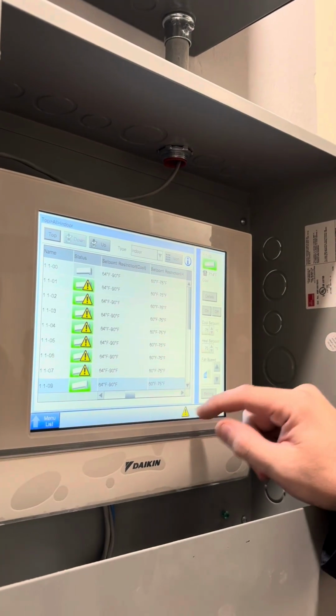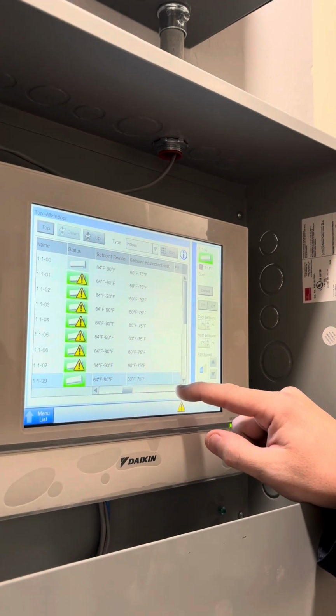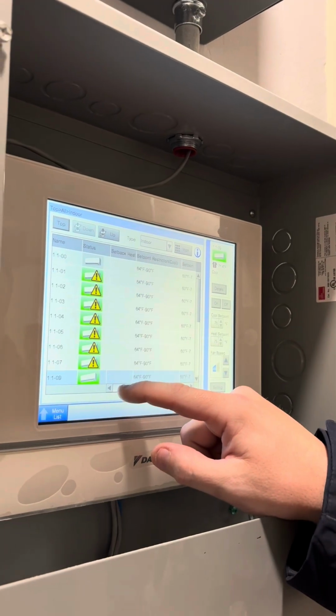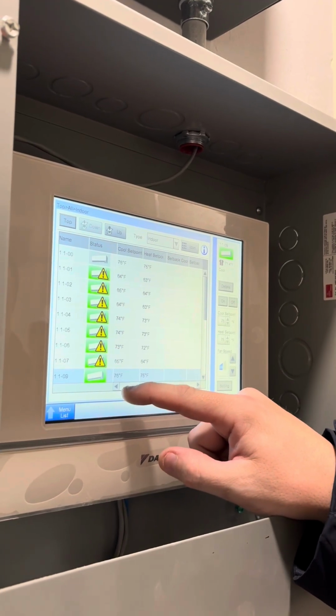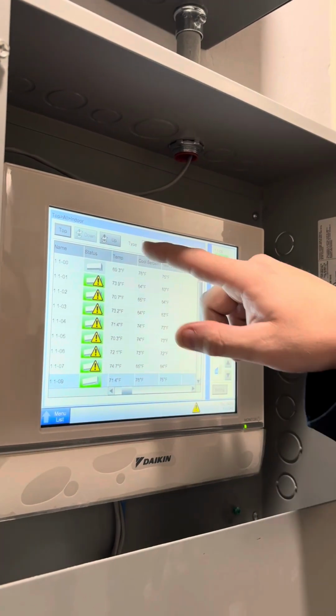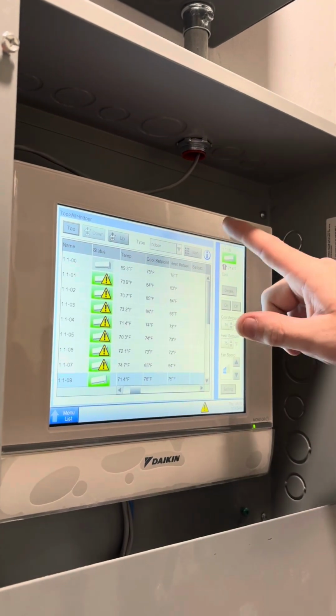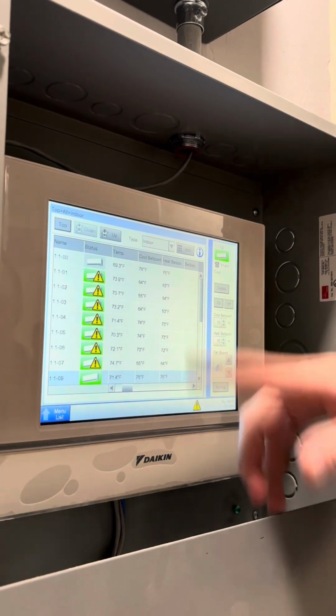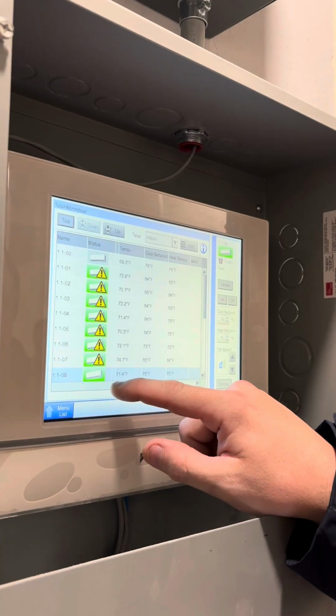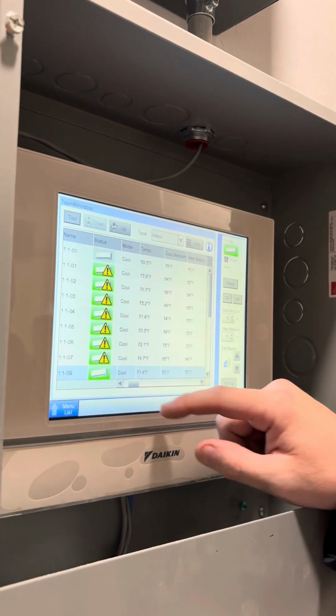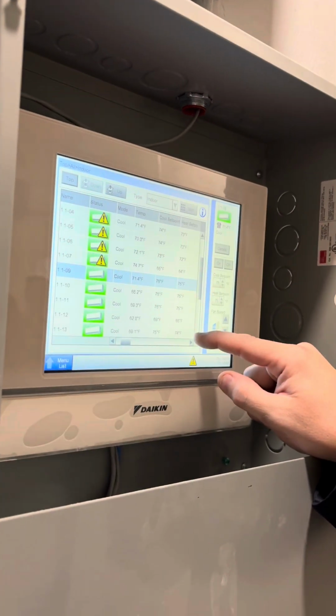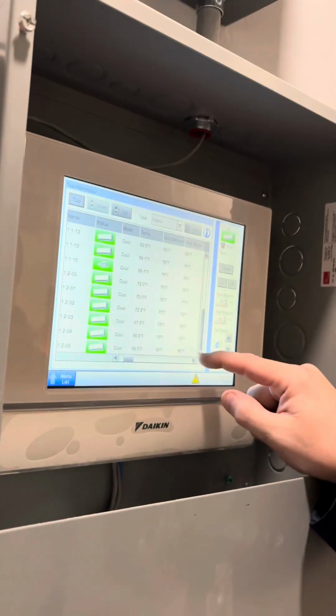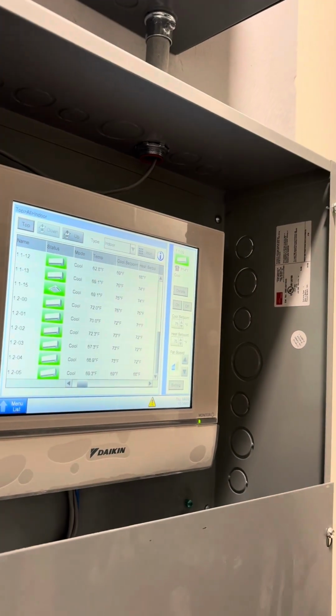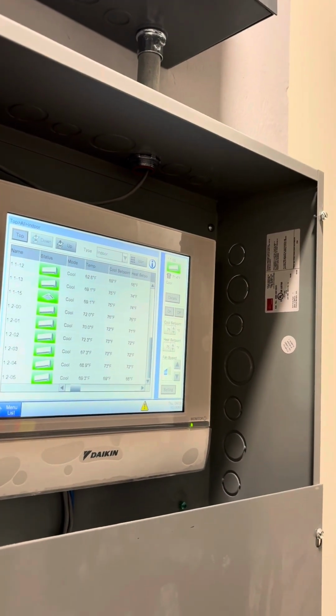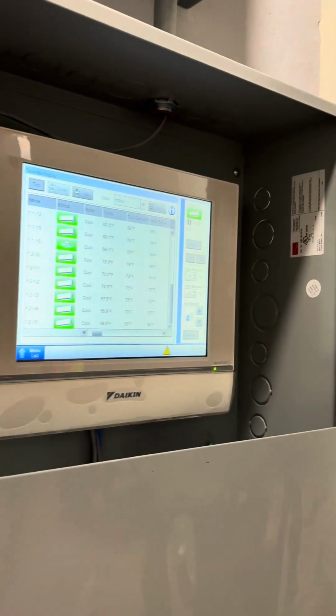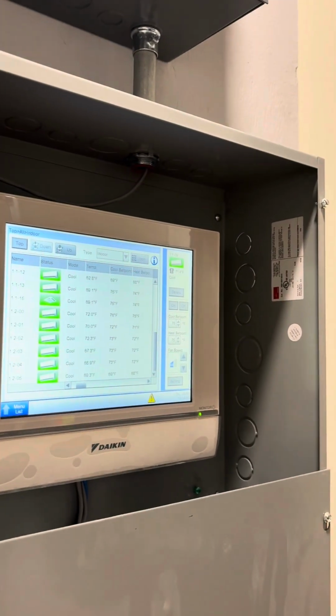So these are the set point restrictions that are on all of them now. Basically, this is where I'll look. What's the temperature in the room? What's my cooling set point? What's my heating set point? And then it'll also tell you which mode each of the units are in. So we've basically flipped them now all to cool. So now the building will be in cooling mode. You won't have to change it till the fall or whenever you get into heating mode.